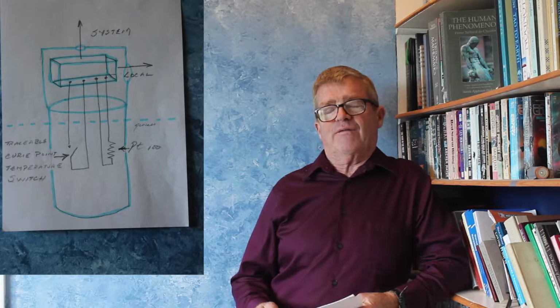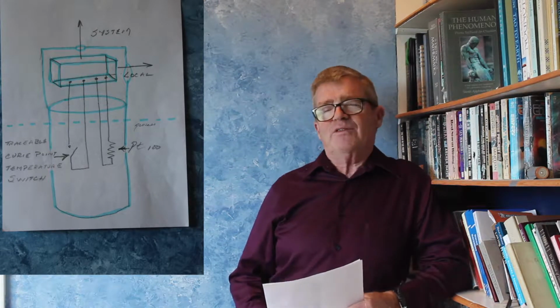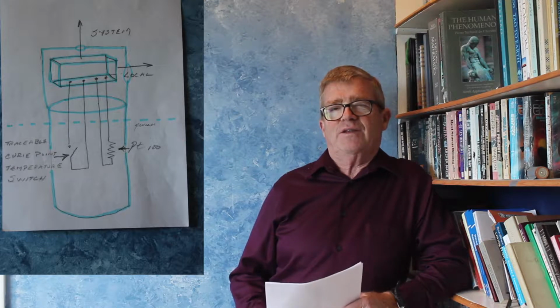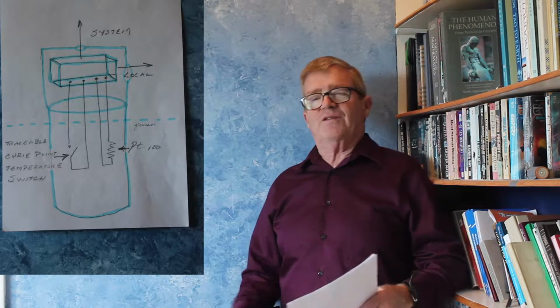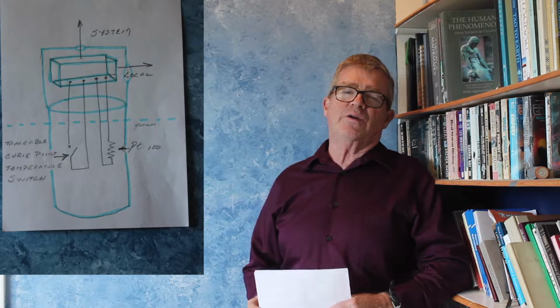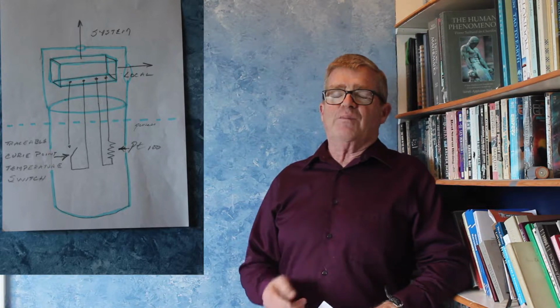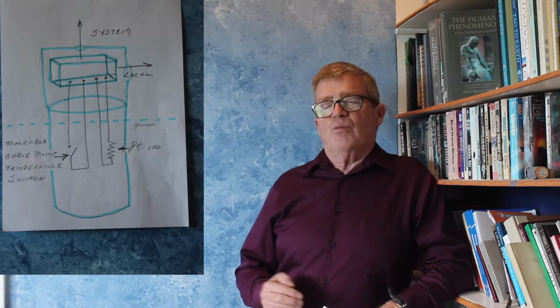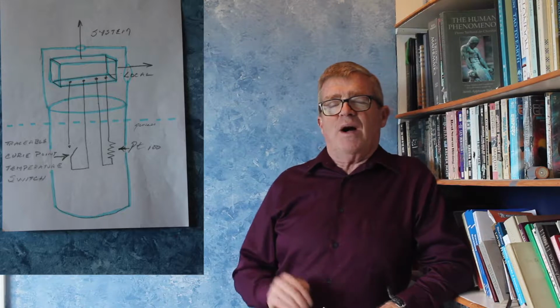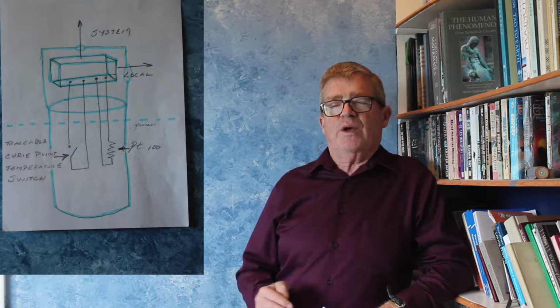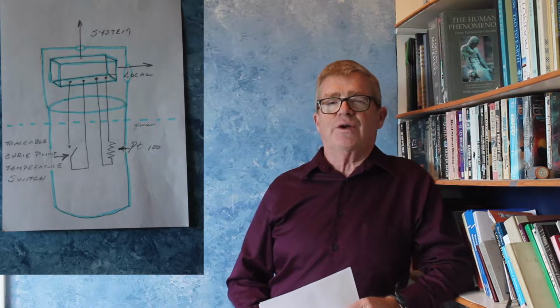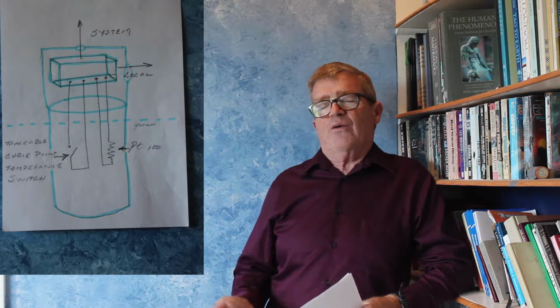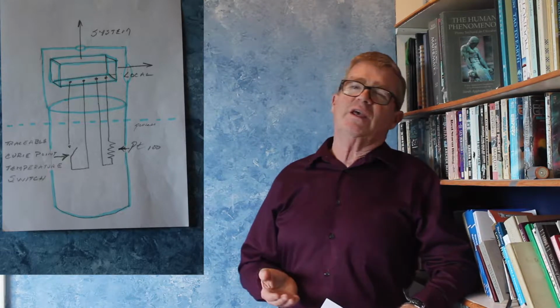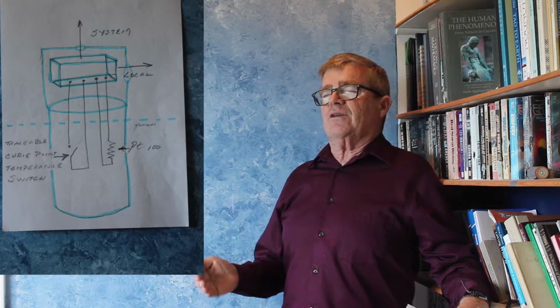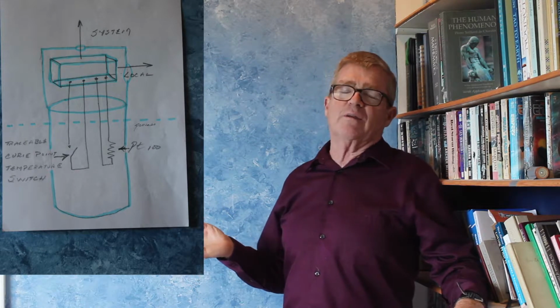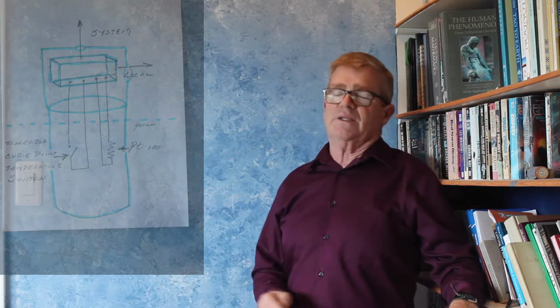Here we have a schematic for what I think is going on in this device. And I must say, I think it's really elegantly conceived and designed. First of all, down on the business end, you see 2 elements. One's a PT100. These have been around for decades. They're very precise and very well characterized. What's new here is that Endress and Hauser has bonded what I call a traceable Curie point temperature switch right onto the PT100. I'll explain why it's traceable and how it works in just a minute. Now up above you see enough software and hardware to execute, manage, and save a whole bunch of calibration events that occur in this device right there on board.